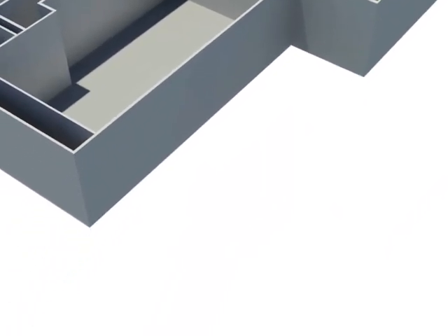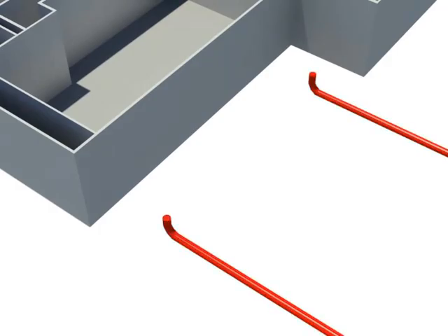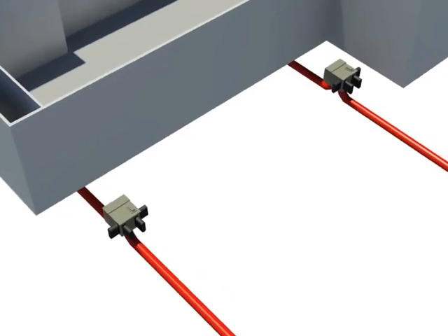Commercial power is delivered to this facility through two separate feeds. This dual power bus configuration is conditioned by power distribution units and two 320 kVA APC uninterruptible power supply units and two 150 kVA Liebert units. These units provide a true redundant A and B feed to the raised floor.